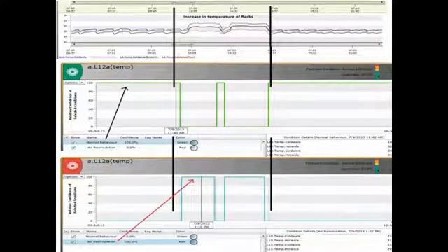Those are normal state temperatures, and then we started pulling blanking panels off a few of the racks, and of course some of the temperatures started to rise. That was identified by this software that we're working on as an abnormal state, and there's a green line that takes a dive here in the second chart, indicative of the fact that something abnormal happened. And I am 100% sure that something abnormal is happening, and so it is a very straight line that goes all the way to the end.